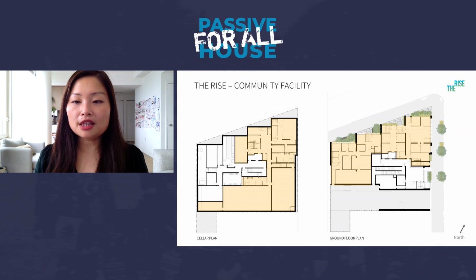You can see in the plan that most of the ground floor is lined with storefronts, which have steel beams above to provide for the large openings. All the community facility spaces are provided with ERVs, and we have provided louvers at the storefronts for the supply and exhaust. Currently, the thermally efficient frames for the triple pane UPVC storefronts do not have an integrated louver, and we're looking at providing an aluminum louver instead.